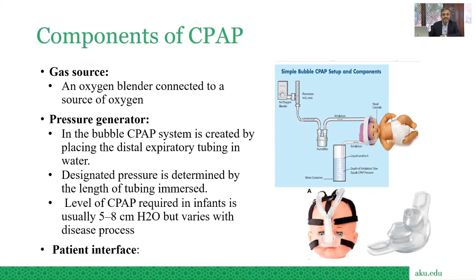Then the patient interface, as I mentioned, can be nasal prongs, which are tightly fitting, or it can be a face mask. The important consideration here is the formation of a seal. If there is no seal, then CPAP does not deliver the PEEP which is required to prevent atelectasis and improve FRC. Coming on to the BiPAP, it basically provides two pressures, inspiratory positive airway pressure and expiratory positive airway pressure, during the different phases of inspiration and expiration. And the interface can be, again, a nasal mask or nasal pillow, it can be an oral face mask, or it can be helmets.